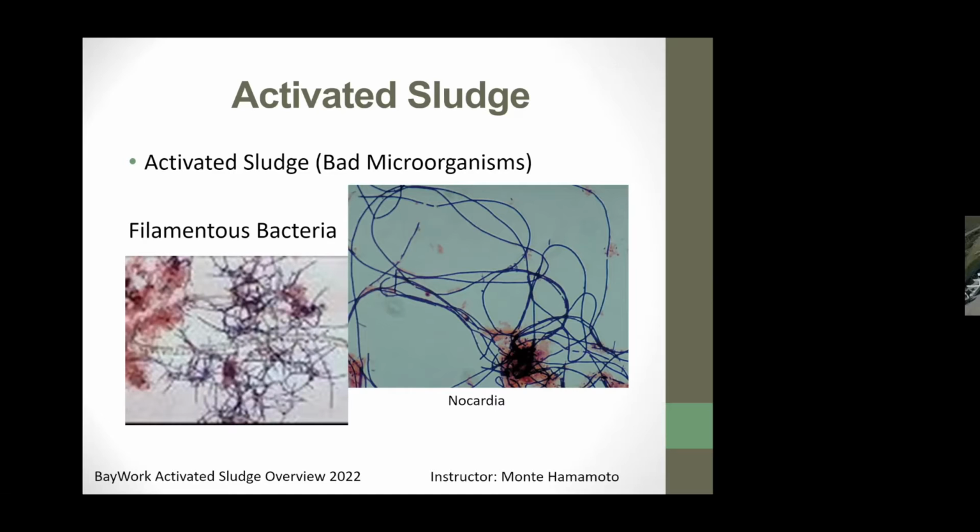There are different trains of thought here. Some people say, hey, I want to ease into it. I want to hit it with chlorine, do my microscope slides, see what shape the activated sludge is in. And then if I can, I'll increase it and I'll just kind of step it up. That takes a while to do. Sometimes it's not as effective, but if you're on the thinner side, that's the proper approach.